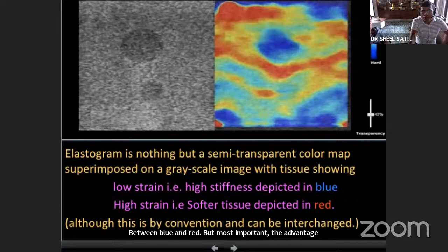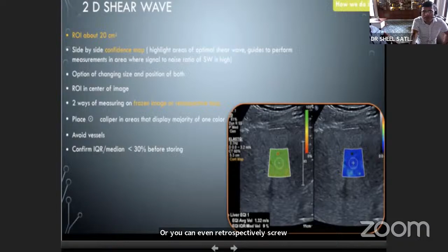The region of interest is in the center of the image, and you ask the patient to breath hold. You see a map. If the map is properly uniform in green, uniform in blue, it's fine. There should be no disturbances in between. This is the most important image. And the best part is you can focus on a specific image, or you can even retrospectively scroll back to where you get a proper image which is devoid of any vessels.